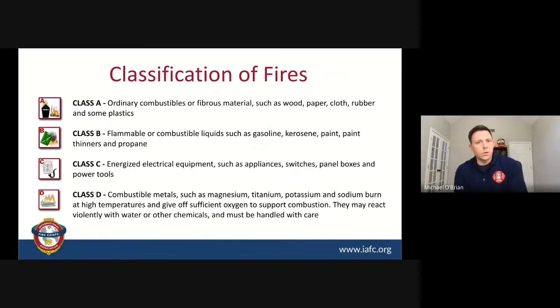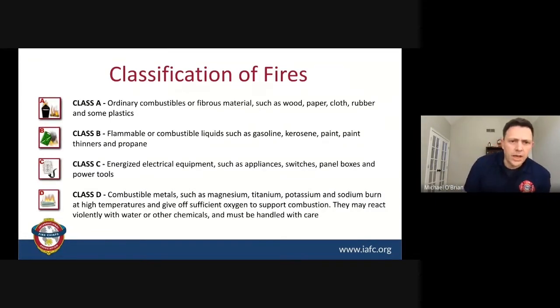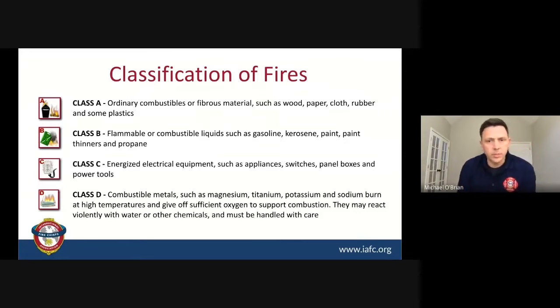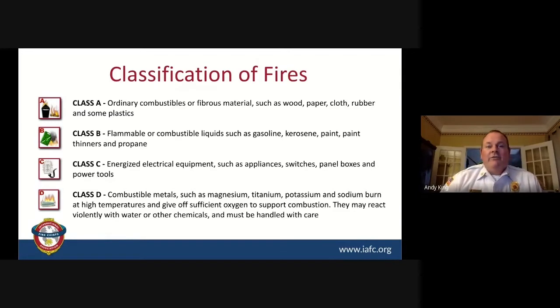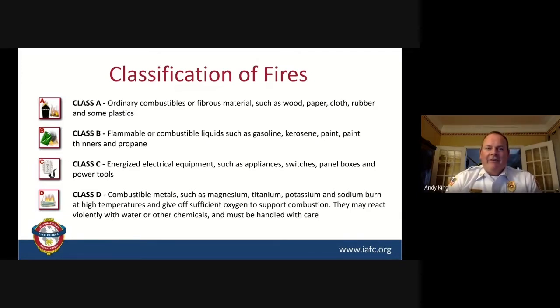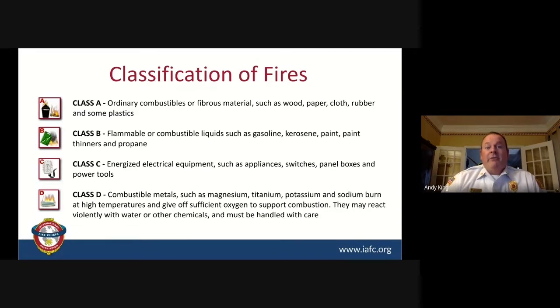Class A is ordinary combustible materials — wood, paper, cloth, maybe some plastics. Class B, we start to get into flammable or combustible liquids. Class C is typically a Class A fire, but it involves energized electrical equipment. The idea is to kill the electricity beforehand before extinguishing it. There are also different types of extinguishers that can be used on Class C in a safe way. And then Class D is the final one, which involves combustible metals. Typically we all think of magnesium — magnesium engine fires — and those are metals that typically can't be extinguished with water, or if they are, you have to be very careful.